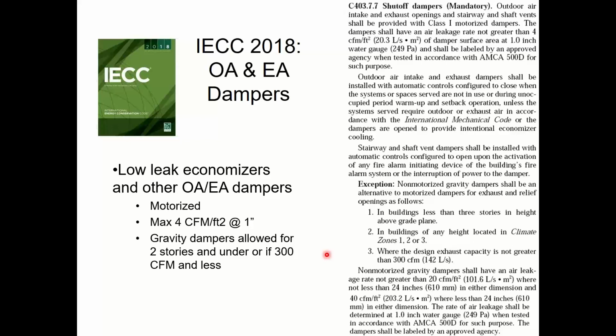The energy code will also require all of my mechanical inlets and outlets of the building, so all my exhaust dampers and all my outside air intake dampers, to have low leak motorized dampers. So low leak is not just a random thing. It's a defined thing. For the international code, the definition of it, if you read up here, not that I want you to read all these code things, is that I have to have no more than 4 CFM per square foot leakage at 1 inch of pressure. That's the definition of it. And to do that, I'm going to have an AMCA certification and an AMCA 500D stamp on the metal, or sticker, saying that it complies with this.